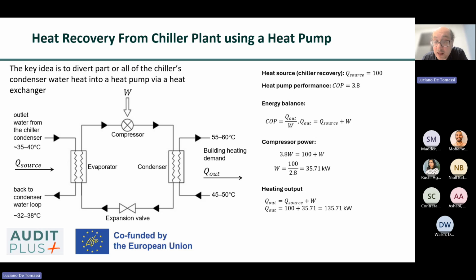depending on the heating system design and load conditions. The heat pump then upgrades the temperature difference between the low-grade condenser water loop as the heat source and the higher temperature heating loop as the heat sink, effectively lifting waste heat to a usable level. The critical design concept in this configuration is simultaneously balancing the temperature levels. The chiller condenser loop provides a stable low temperature heat source at 35 Celsius degrees.